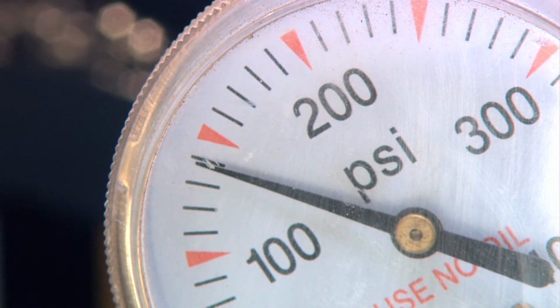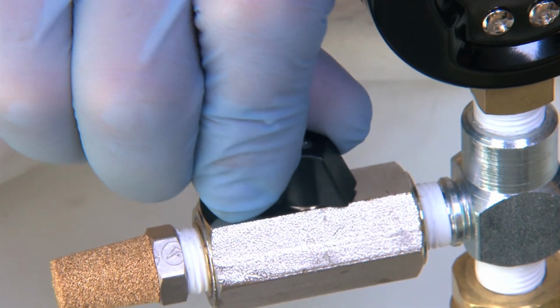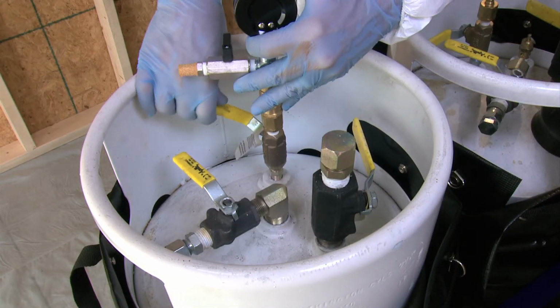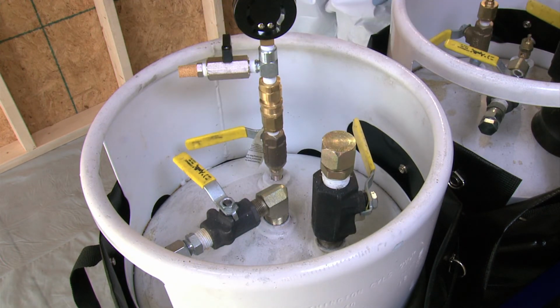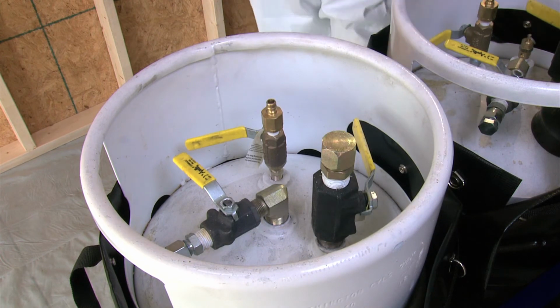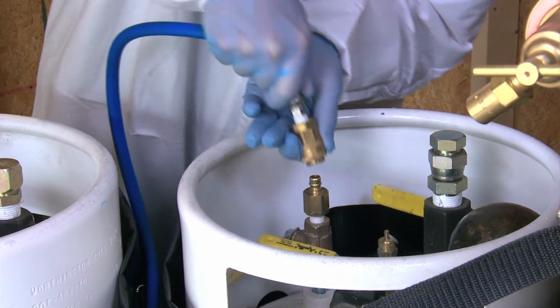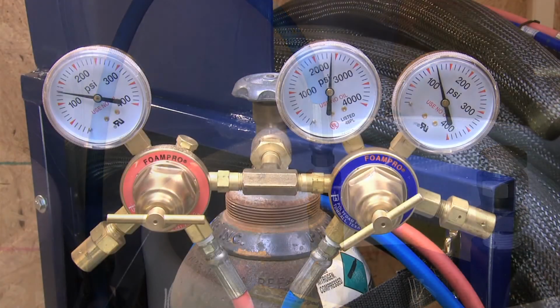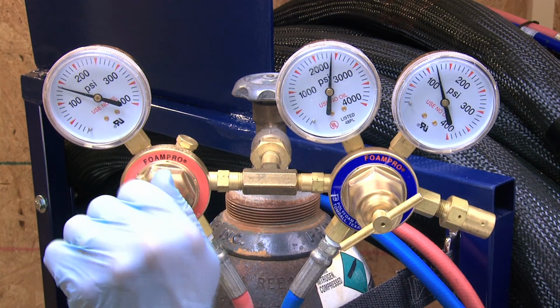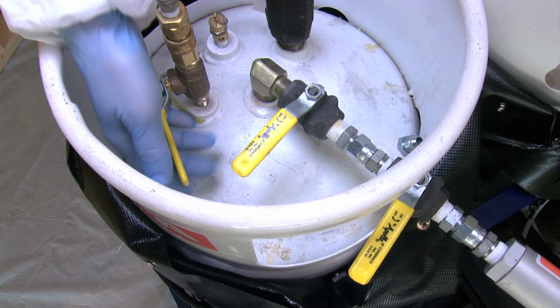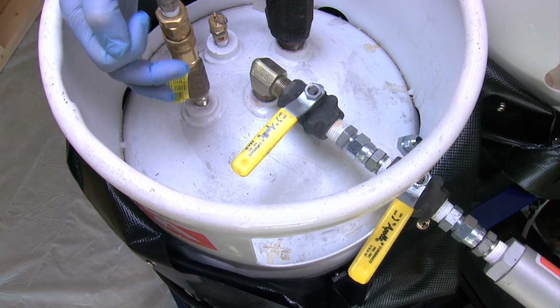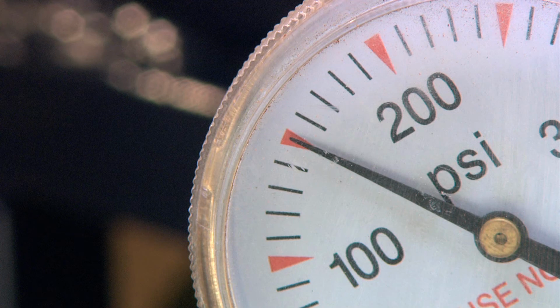Slowly open the pressure release valve to allow pressure to drop to a level that is a minimum of 10 psi below the desired level. Close the pressure release valve. Close the nitrogen valve on the chemical cylinder. Remove the pressure release valve from the chemical cylinder. Reconnect the nitrogen hose to the cylinder. Set the nitrogen pressure on the regulator to the desired pressure. Open the nitrogen valve into the chemical cylinder to equalize the pressure to the desired level. Now you may complete the calibration process, making sure that you do not exceed 200 psi in either chemical cylinder.